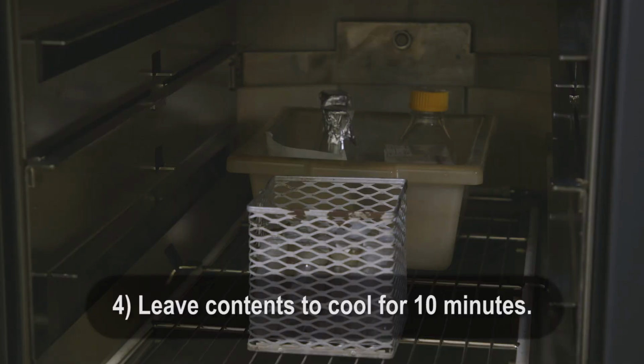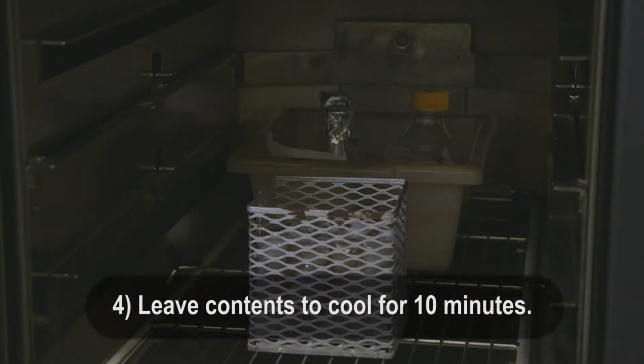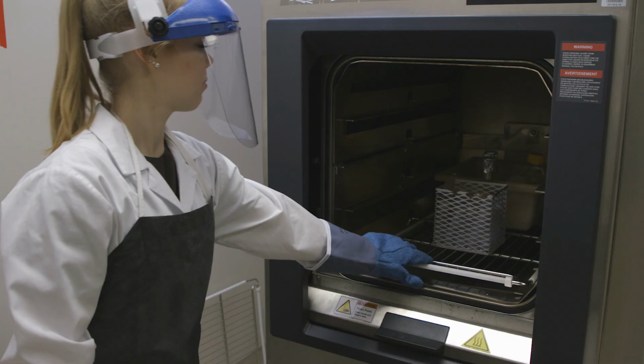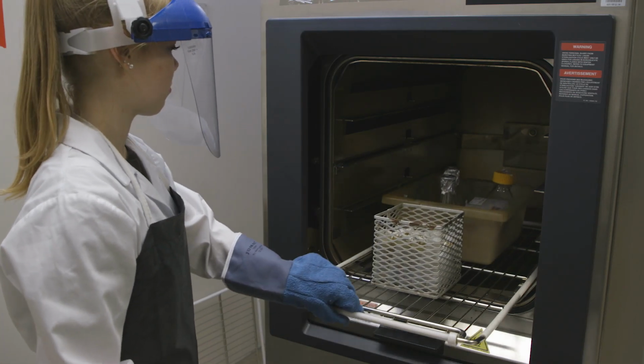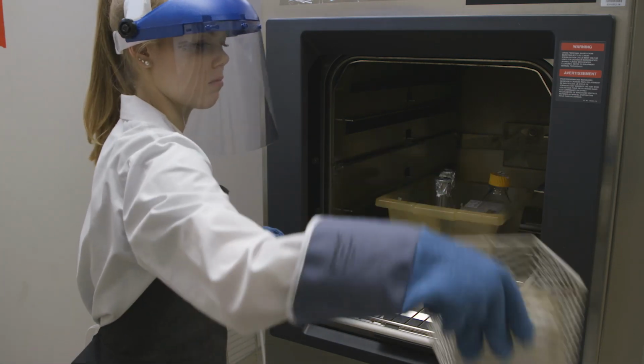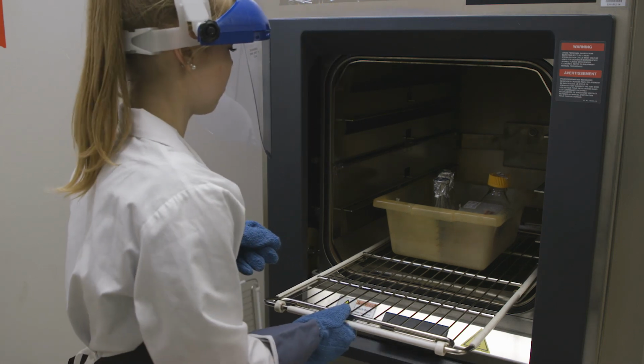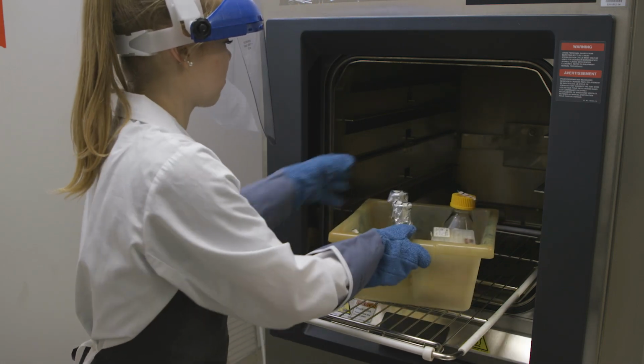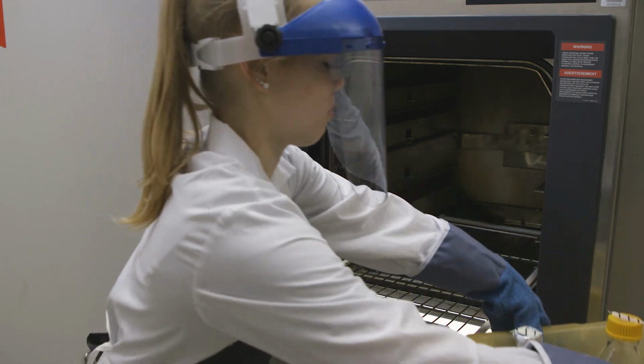Do not agitate containers of superheated liquids or remove caps before unloading. Superheated liquids can explode if they are shaken or moved too quickly during the cooling process. After 10 minutes, you may now remove your items from the autoclave. Do not leave items in the autoclave overnight. Be sure to verify that temperature-sensitive autoclave tape has changed color.